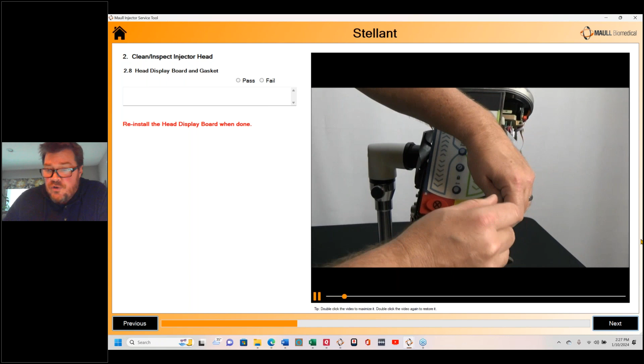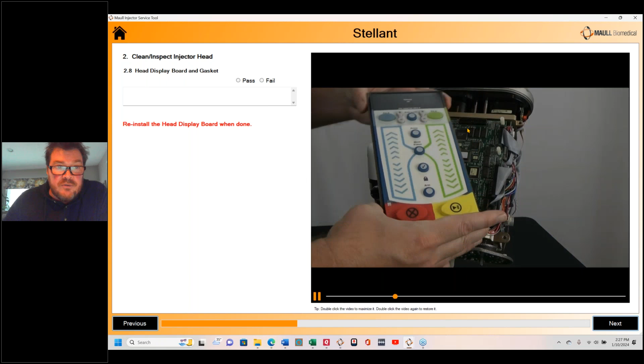Now we're getting inside the injector head here. I'm going to move this down a little bit. So we're getting inside here. We need to take the front display board off. We have some cleaning and checking to do to make sure contrast didn't get onto the back of the board. And there's also this gasket right here. It's not a gasket that's replaced annually because it's glued on, but we want to make sure that we clean this metal gasket off.